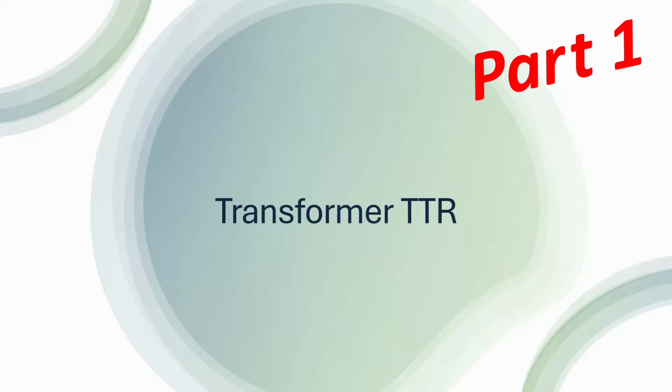So here we're going to talk about transformer TTRs, and one of the most important things I try to remind people is that when you're doing the transformer TTR, if you can do it single phase, you know what you're doing. It doesn't matter if you have a three phase, whatever, 20 degrees clock shift, the single phase TTR always works every time. So I recommend doing that, but you have to understand that we're talking about the coupling of one coil to another.